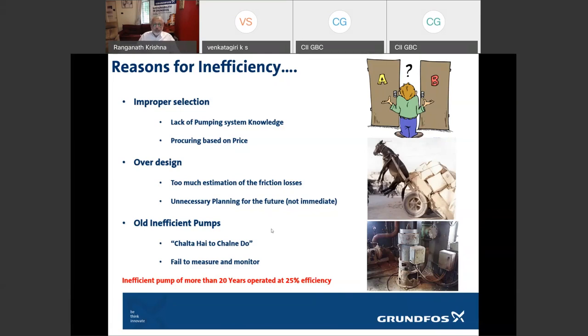The other situation in India is this nice phrase, chalta hai to chalne do. You see that pump there on the right? It's an old pump, I don't know, 25 years old, 30 years old, but nobody wants to change it because it has not failed. We don't measure or monitor what the requirement is now. So we have inefficient pumps and some of them run at 25% efficiency. The classic case was in a very large steel mill, when we went and replaced a 25 kilowatt pump with a 2 kilowatt pump, and it worked very well. So one needs to look at your basic engineering practices before you get into technology.